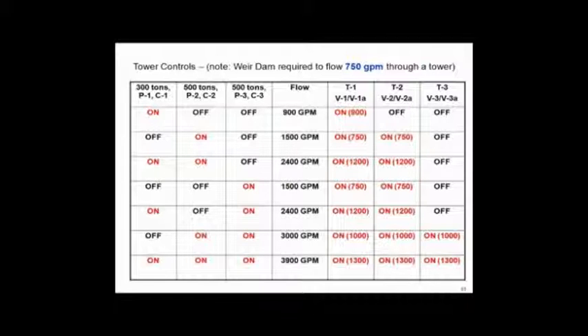Let's turn pump 1 and chiller 1 off and let's turn on number 2. We've got chiller 2 on line, pump 2 on line, chiller 1 and chiller 3 off. Total flow rate now is what? 1500 GPM. Great. So now we've got 1500 GPM going out to the towers. How many towers are going to run at what flow rates? Well, let's start off in a condition. Let's let T1 and T2 be on. Let's take T3 off and valve it off. And that would give us if it was balanced properly what? 750 GPM per tower. Is that an acceptable operation? Absolutely.